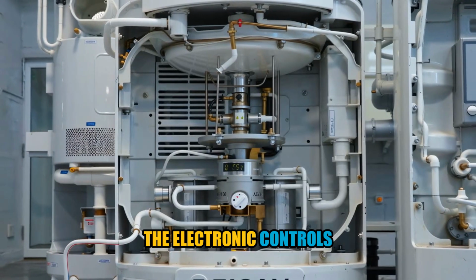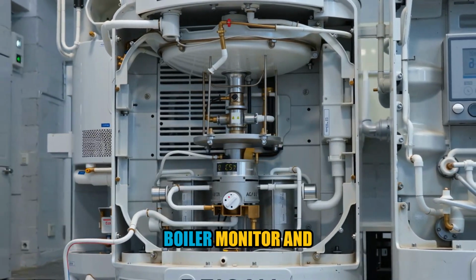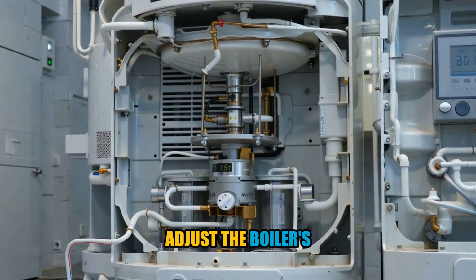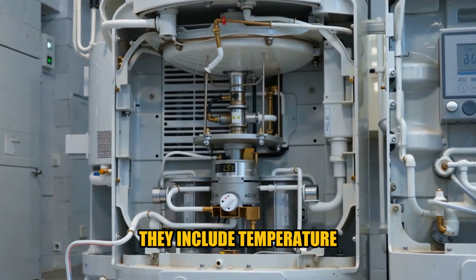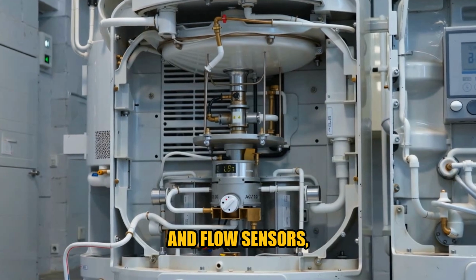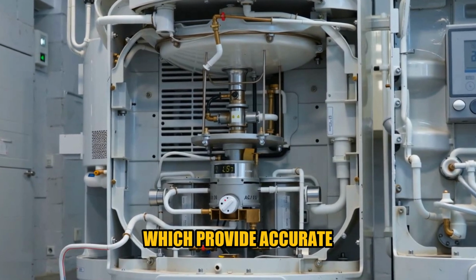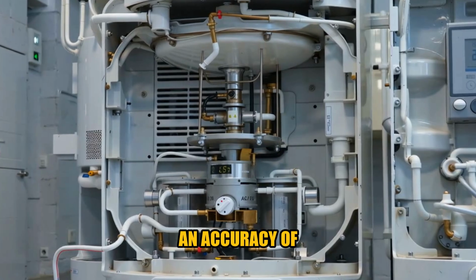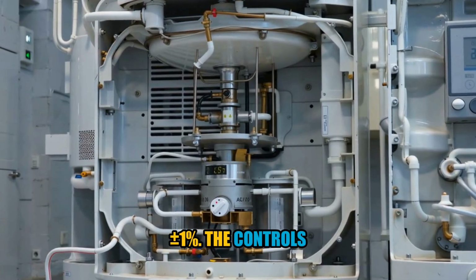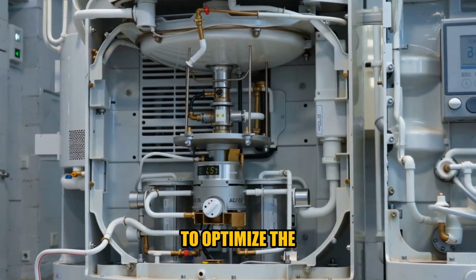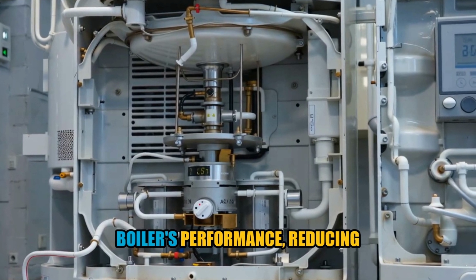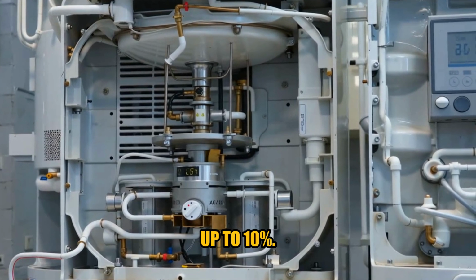The electronic controls in a condensing boiler monitor and adjust the boiler's operation in real time. They include temperature sensors, pressure sensors, and flow sensors, which provide accurate readings, typically with an accuracy of 1%. The controls use this data to optimize the boiler's performance, reducing energy consumption by up to 10%.